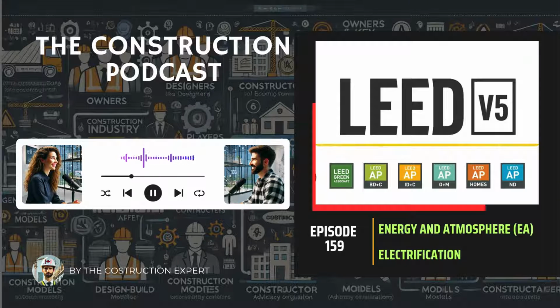Yes, a few practical exceptions. For space heating, if you're in a really warm climate zone 0 to 2, think Florida, Hawaii, Southern California coast, where you barely need heating anyway. Exactly. The heating load is tiny compared to cooling. So they don't need to meet the space heating COP requirement there. It avoids unnecessary burden for minimal gain. Also, if you have a supplemental heating system that's only for very low temperatures, like a combustion backup for extreme cold snaps, that part is excluded from the COP calculation. Again, acknowledging practical needs and harsh conditions, as long as it's not the main system.